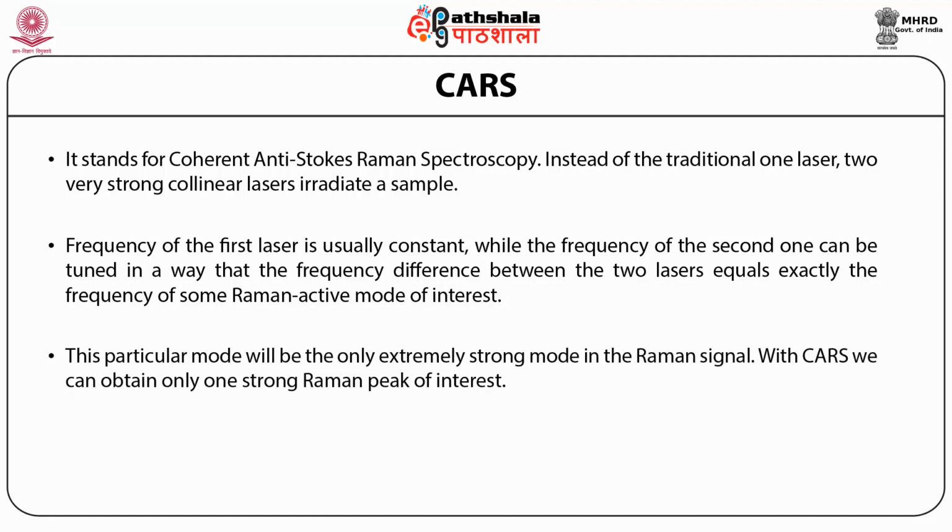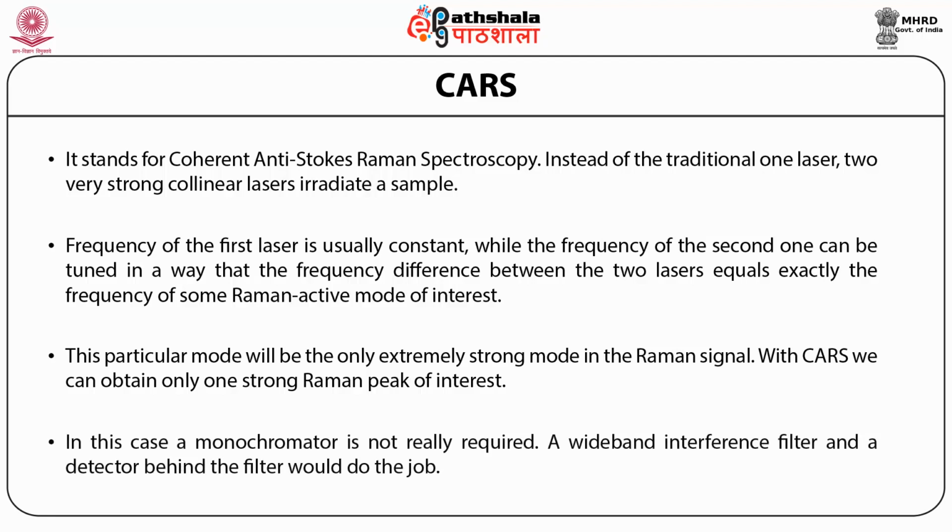This particular mode will be the only extremely strong mode in Raman signal. With CARS, we can obtain only one strong Raman peak of interest. In this case, a monochromator is not really required. A wideband interference filter and a detector behind the filter would do the job.